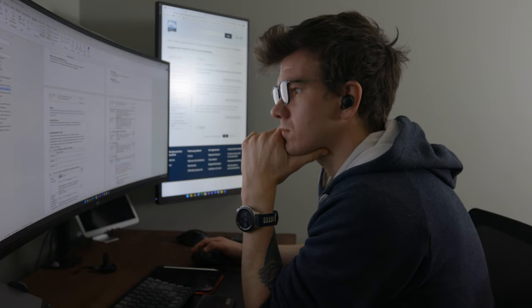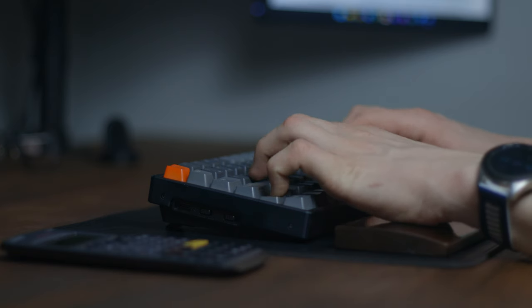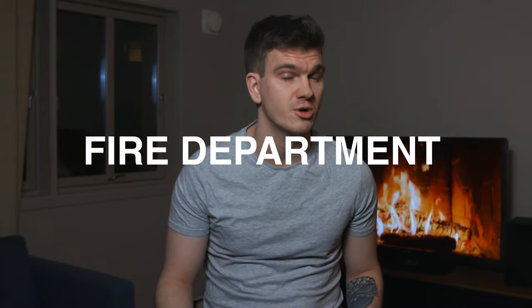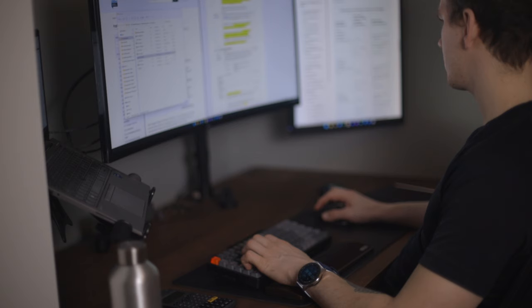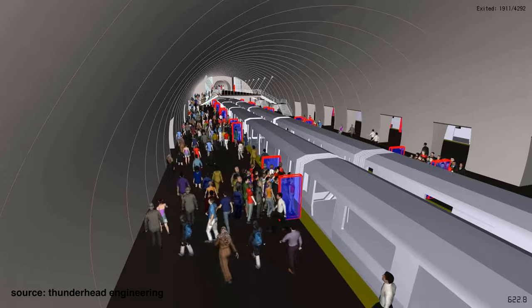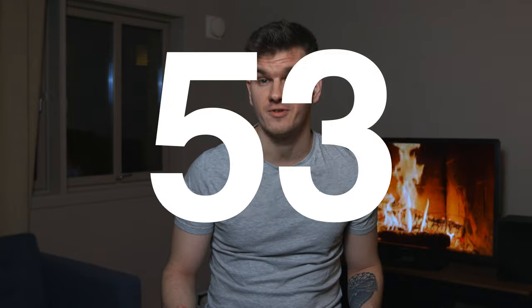After sketching off the drawings, I get it up in the report, running down the criteria given for the specific risk category that the building is set in, using the regulations' 17 chapters on fire safety — ranging from the building's load-bearing capacity to securing the safety of the fire department in an emergency situation. If there are some parts of the regulation that seem a bit redundant for the specific building, or even hard to achieve, it might be needed to do some extra analysis, calculations, or simulations to prove that the fire safety of the building is achieved without that specific criteria. So far during my 53 projects, there's been the need to do that for 60% of them, so it's quite a common practice.